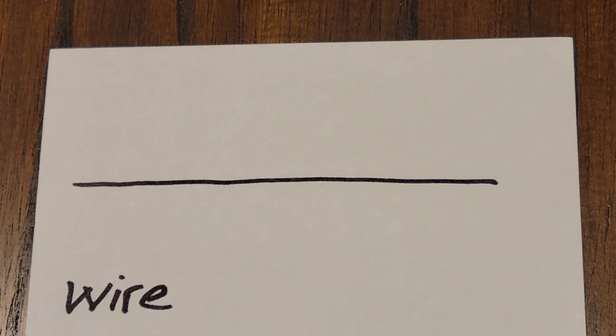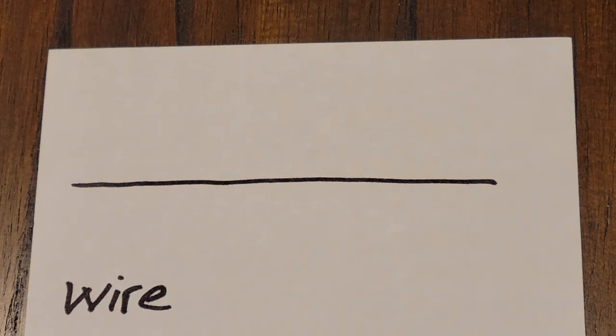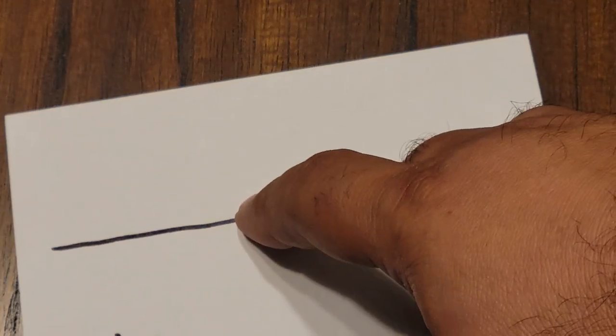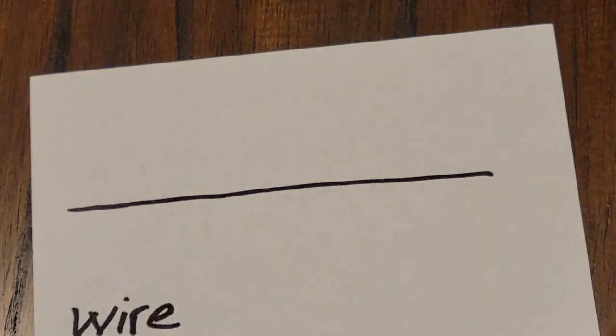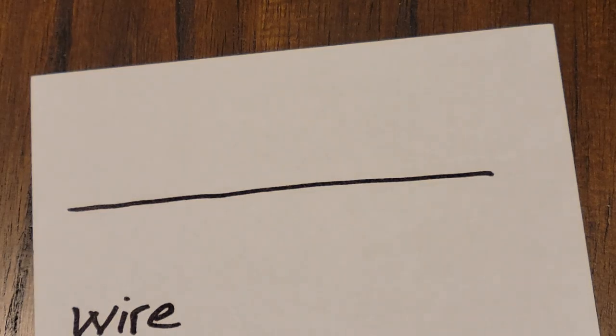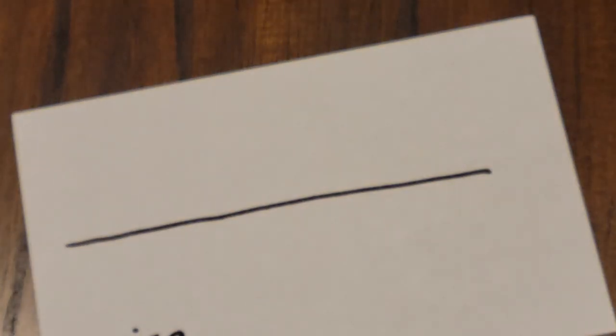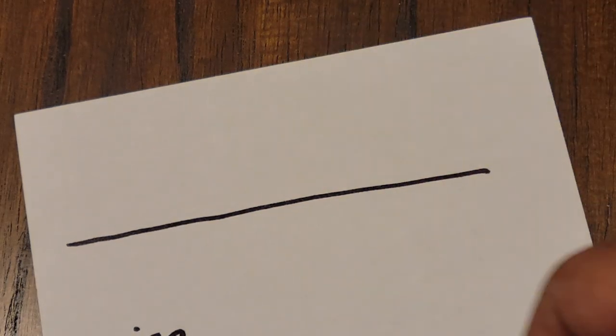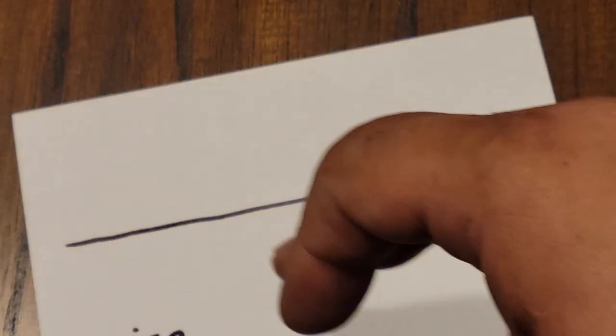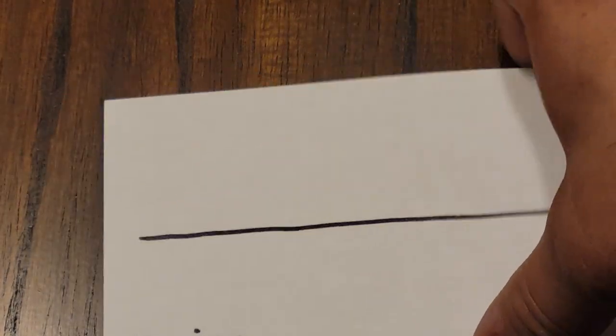That's a wire. In more complex circuits, you might see some letters on either side of it. BRN, for example, it would be brown. BRN slash BLK, that is brown with a black stripe. Whenever there are two colors on a wire separated by a slash, the primary color is the first set of letters. So brown would be the primary color. And then the tracer, if you will, or the stripe would be the second color. So brown with a black tracer would be BRN slash BLK.